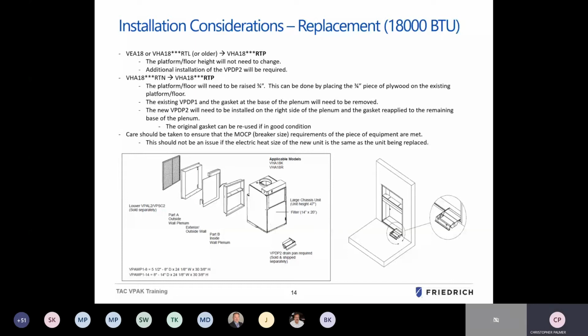In addition, the addition of the VPDP2, which was mentioned earlier, from the VPDP1 would be required. Moving the pan from the left-hand side of the base of the plenum to the right-hand side, as well as replacing or repairing the piece of gasket taken off from the right side and implementing it and sealing it against the left-hand side where the previous drain pan was removed. The original gasket can be reused if it is in good condition, but we do offer the gasket as a whole piece to replace altogether if necessary. Care should be taken once again to make sure that breaker size requirements are appropriate, and it shouldn't be an issue once again if the heater sizing has been taken into account ahead of time.